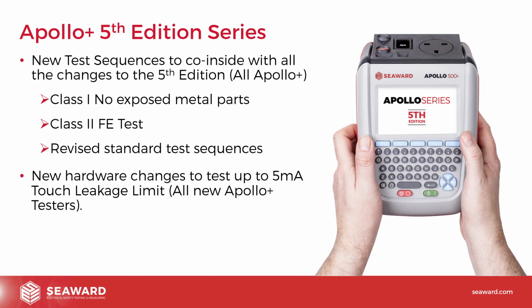The measurement range on the tester was actually up to 3.5. We've had to extend that through hardware changes and obviously firmware changes. And also all of the new test sequences will have the test limit changed for the 5 milliamps. So effectively with the Apollos, that's the main change. We've changed the test sequences. There will be a new firmware coming out, which will be available for existing users to download free of charge. Obviously, the new products will include the firmware anyway, and they will include the hardware changes too. Users who've got an existing Apollo won't have the hardware changes, obviously.